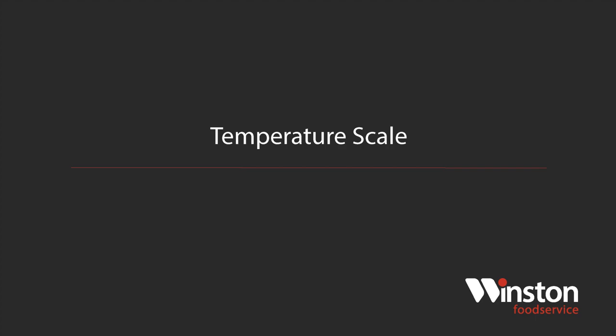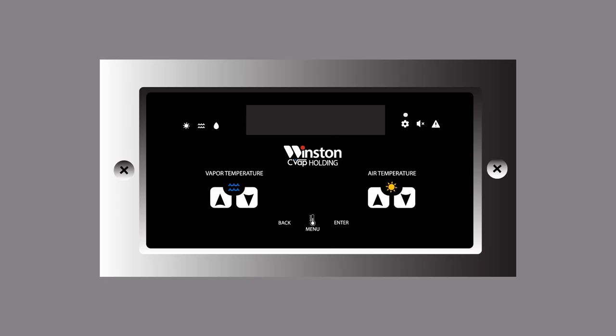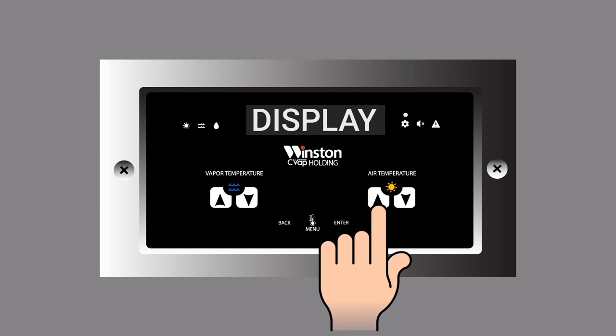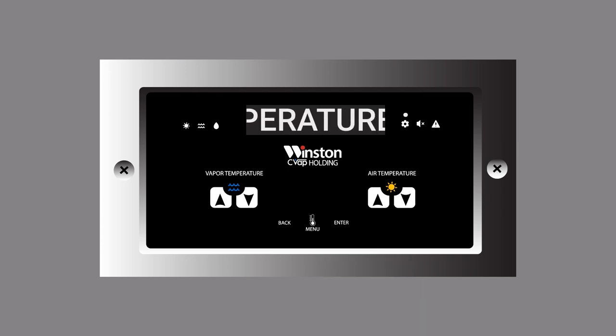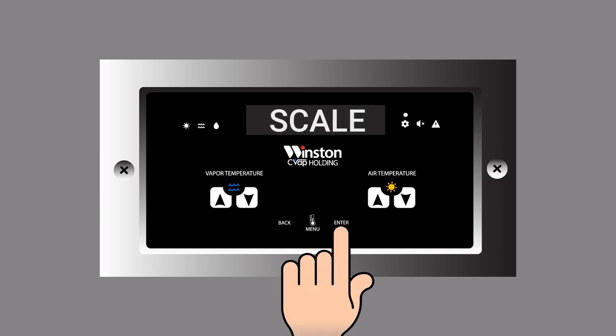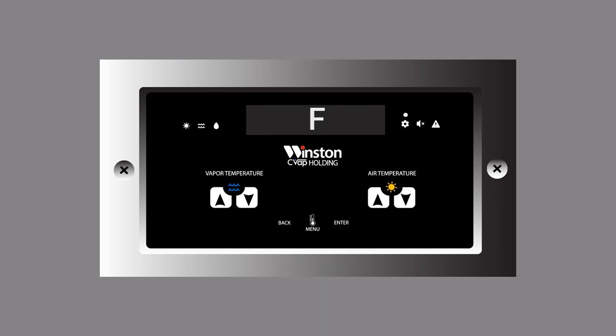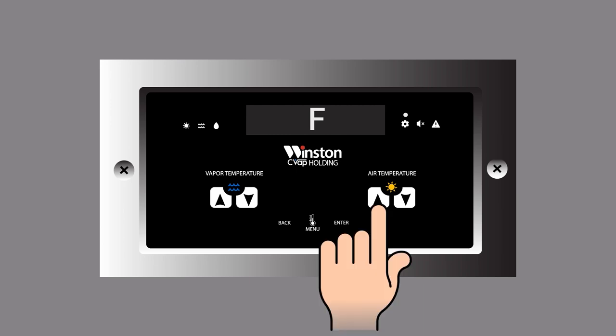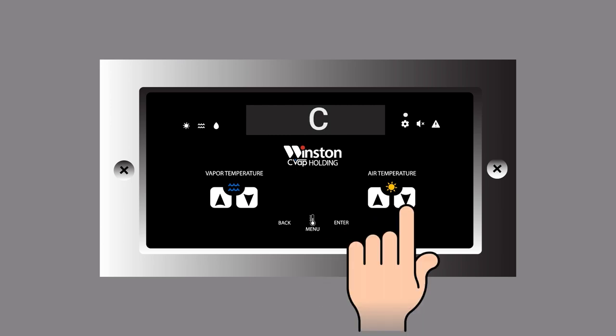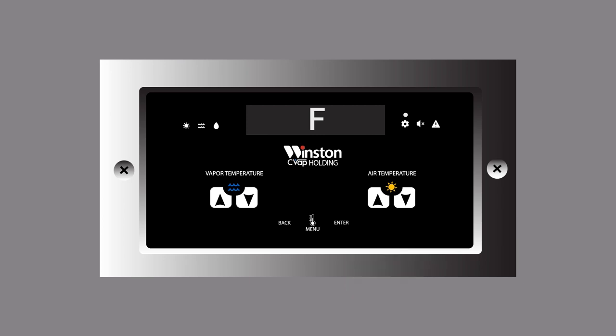Temperature scale. This allows the user to set the temperature scale to either Fahrenheit or Celsius. With display being displayed, press the air temperature up button and temperature scale will be displayed. Select Enter. Either F or C will be displayed. Using the air temperature up and down button, set the temperature scale to either F Fahrenheit or C Celsius. Select Enter. Temperature scale will be displayed.